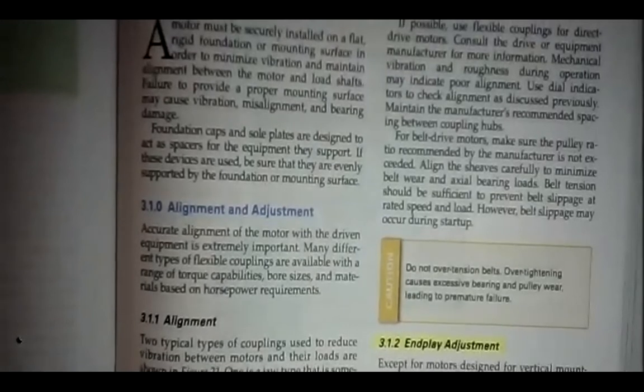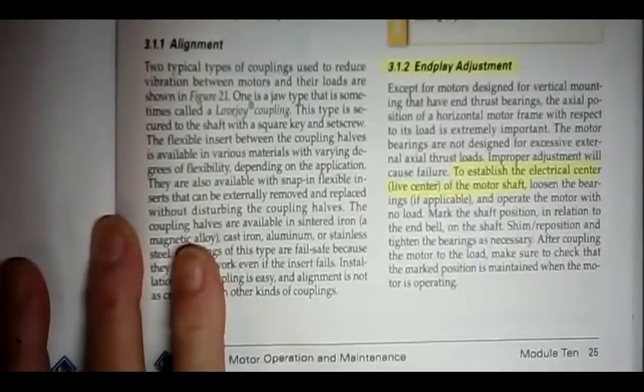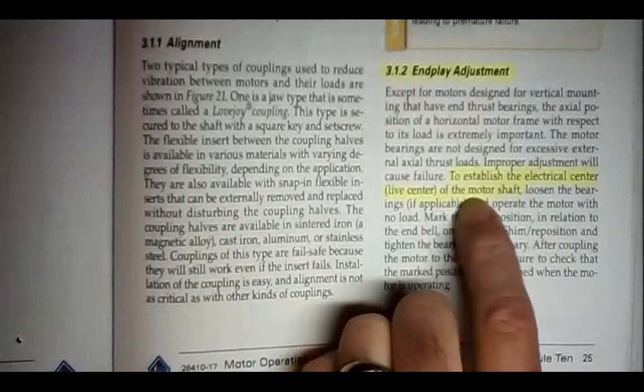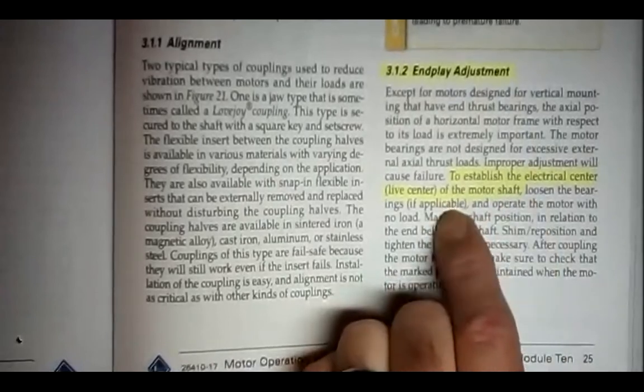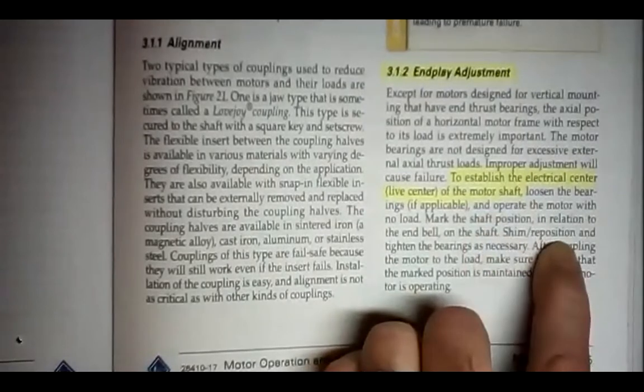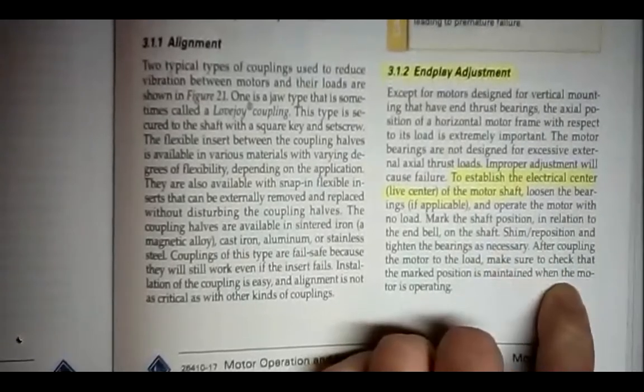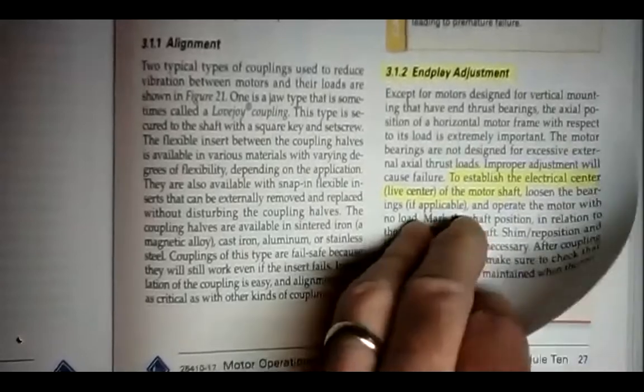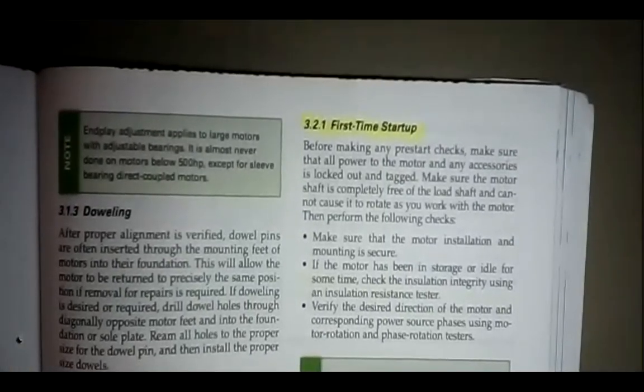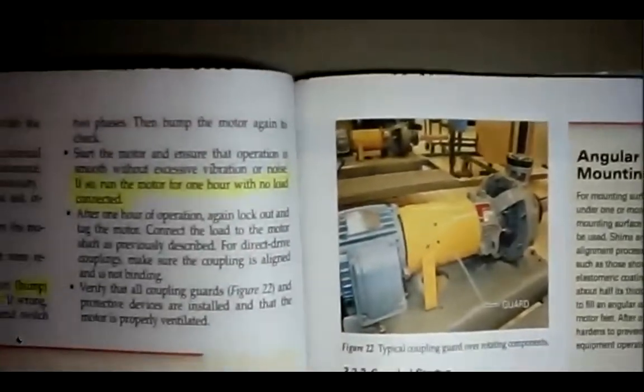On page 25, they're talking about motor installations and commissioning guidelines. So, on page 25 on the right-hand column, end play adjustment. To establish the electrical center of the motor shaft, loosen the bearings, if applicable, and operate the motor with no load. Mark the shaft position in relation to the end bell on the shaft. Shim reposition and tighten the bearings as necessary after coupling the motor to the load. Make sure to check that all the marked positions is maintained when the motor is operating. So, you don't want it to be under distress. 3.2.1, first time startup. That's the only thing that I highlighted. I guess there's information on the next page that we need to know that this is initial startup.